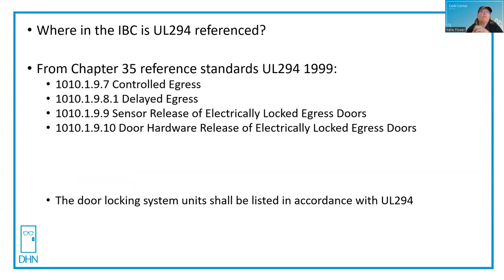UL 294 1999 edition is referenced by Section 1010.1.9.7 for controlled egress, 1010.1.9.8 for delayed egress, 1010.1.9.9 for sensor release of electrically locked egress doors, and 1010.1.9.10 for door hardware release of electrically locked egress doors.